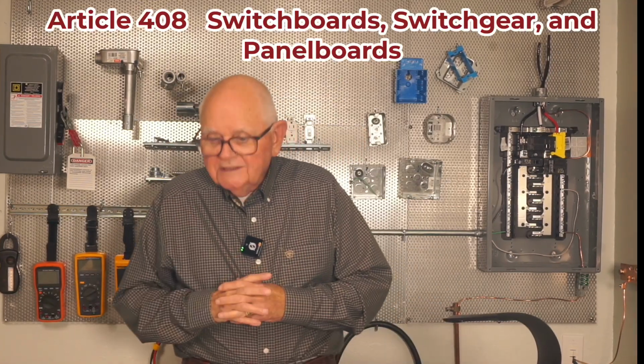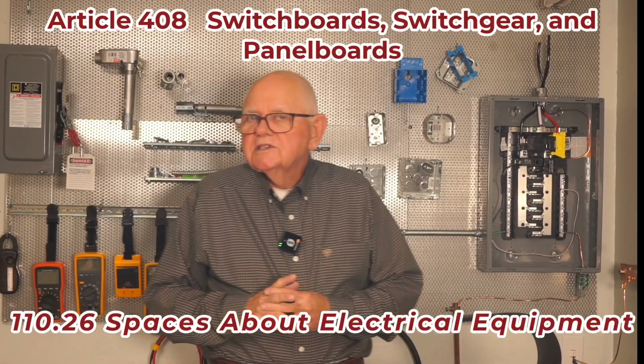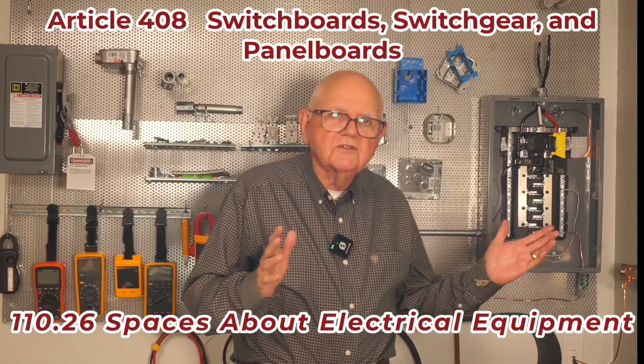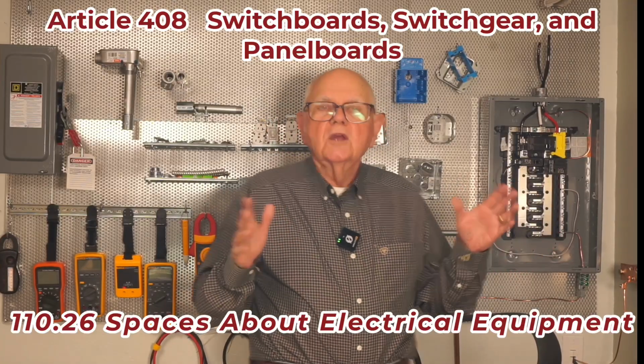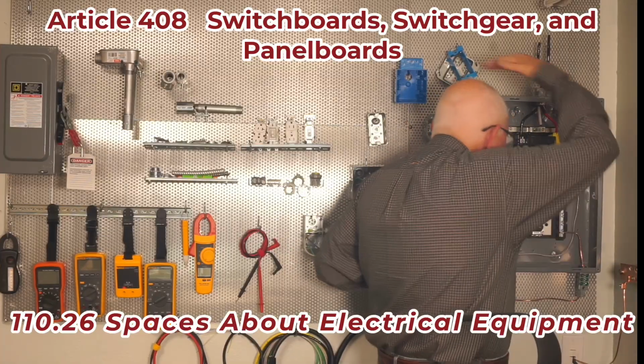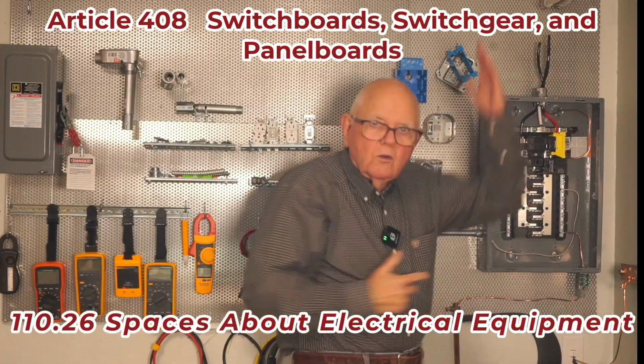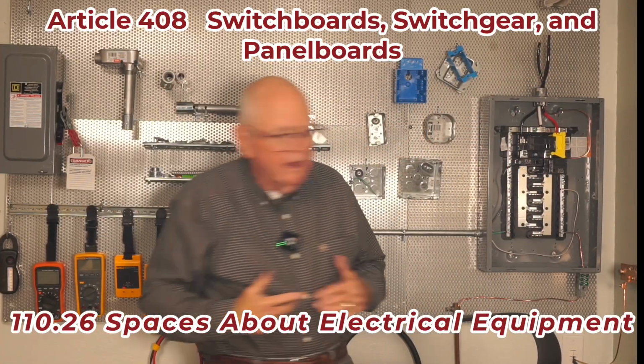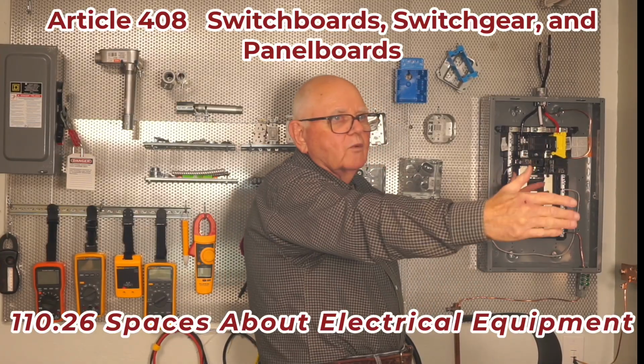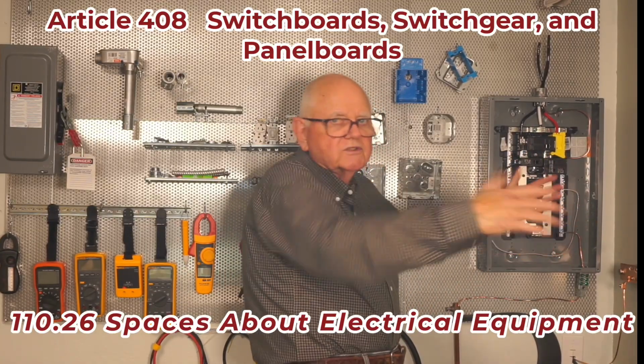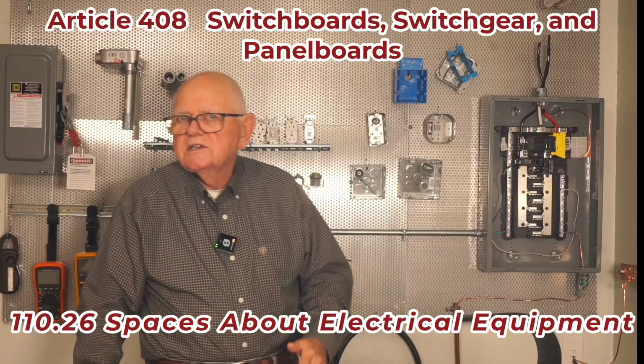Another item, 110.26. 110.26, spaces about electrical equipment. Bottom line, when I come in here to work on this panel board, I've got to have enough elbow room. I don't want to hit my head on anything. I don't want water dripping on top of me. And from this panel board to out here, what's behind me, what are those distance requirements? That's all found in 110.26.